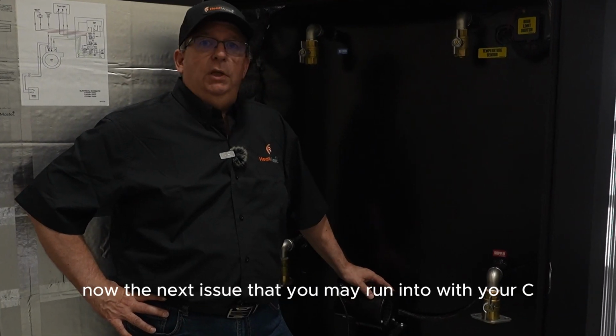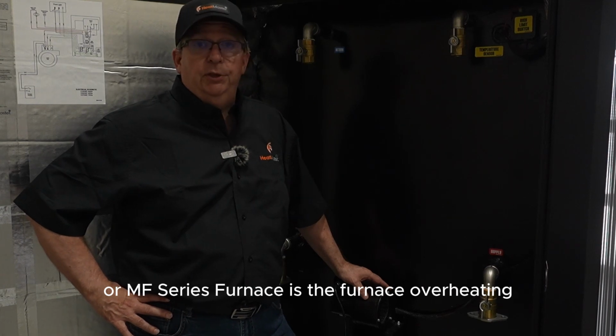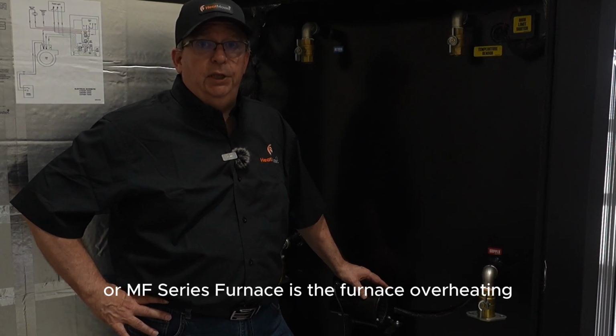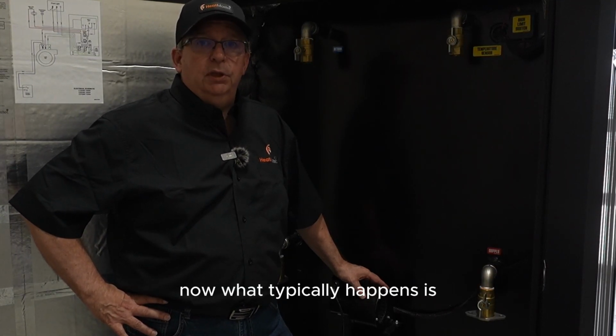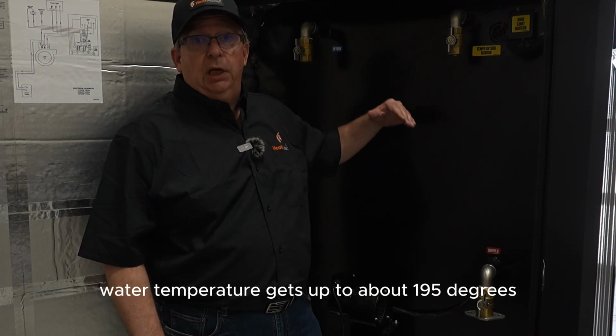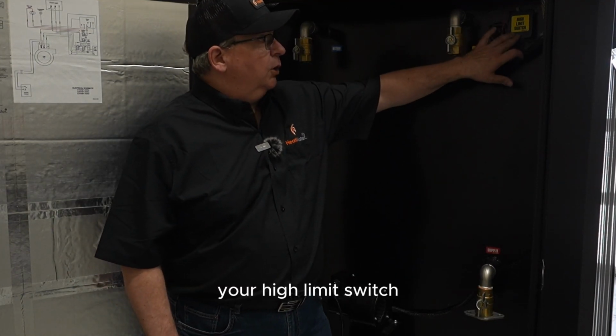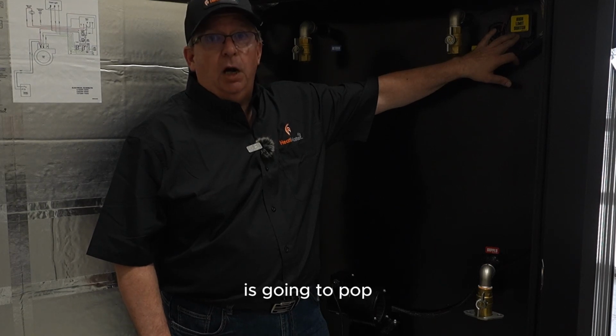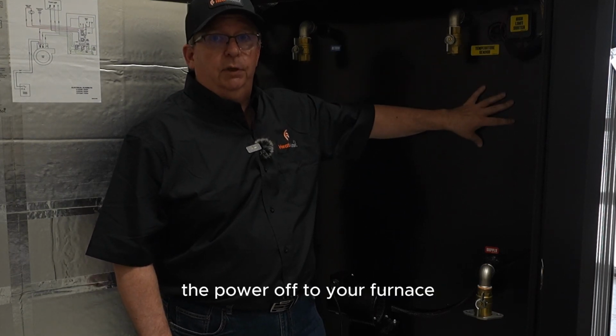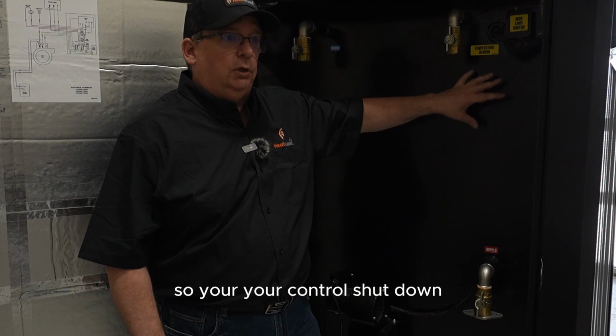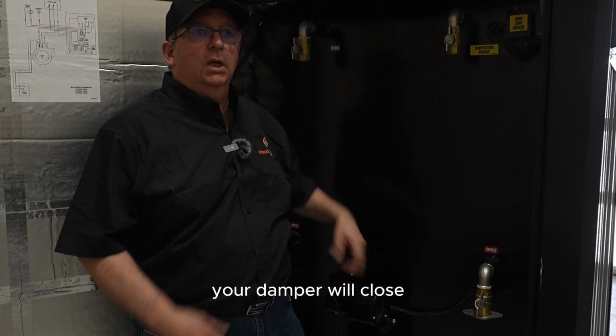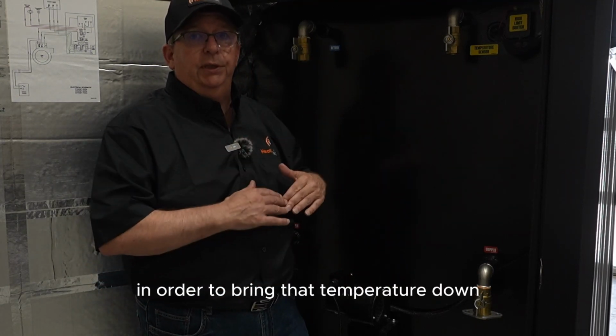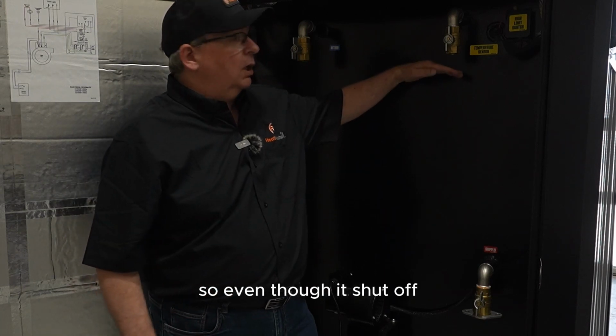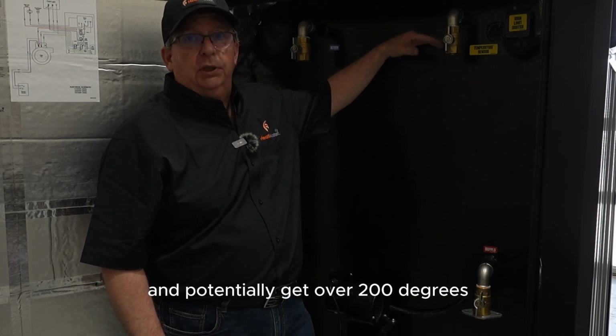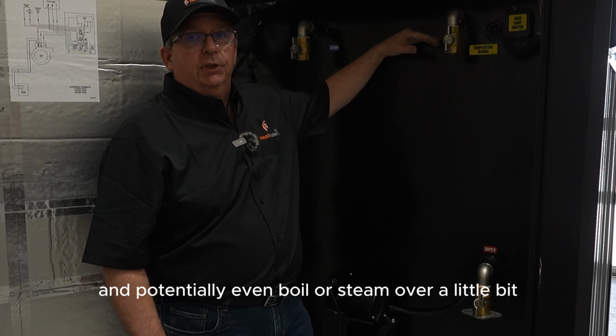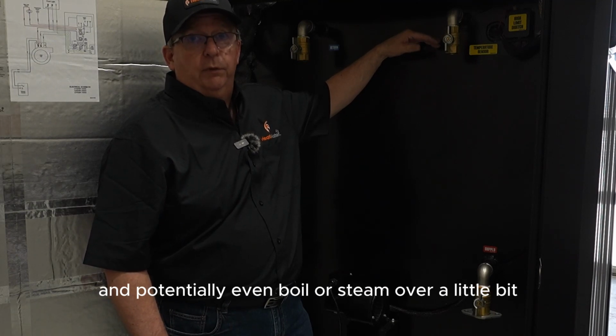Now the next issue that you may run into with your C or MF series furnace is the furnace overheating. What typically happens is once the furnace water temperature gets up to about 195 degrees, your high limit switch is going to pop, and that's going to basically turn the power off to your furnace. So your control will shut down, your damper will close, and it's going to try and seal off the furnace in order to bring that temperature down. Even though it's shut off, that temperature can still rise and potentially get over 200 degrees and potentially even boil or steam over a little bit.